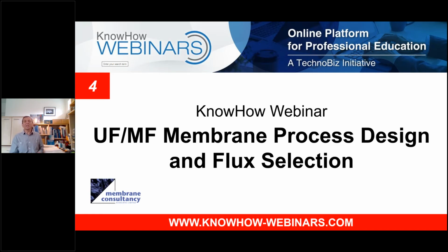So choosing the flux is a compromise, if you like, between capital costs, which are reduced by having a high flux, and operating costs, which are reduced by having a low flux. Somewhere in the middle, there's an optimum flux, which you might call a sustainable flux for that process, and that will be the ideal flux to choose. So it's clear that this will be the most important decision that a membrane process designer will have to make. Depending upon the flux, you might have a design that has a lot of cleaning and a lot of operating cost, or you might have a design with less. So process design and flux selection go hand in hand and are the critical issue, if you like, for the membrane process designer.